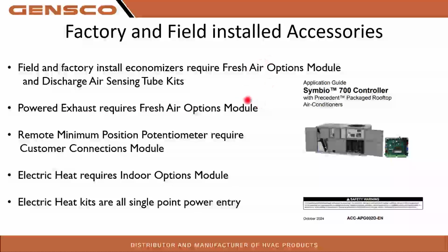Again, powered exhaust, you're going to require the fresh air options module. It's going to plug both into here. Also, if you enable economizer in the app, it's going to look for the fresh air options module. And if you don't have it installed, it's going to prompt an error code. This board, the fresh air options module, is the same as this board, but with a different address. The indoor options module will sit above the heat strip, where the heat strips go right here. The indoor options module will sit up here, and I have better pictures of that.